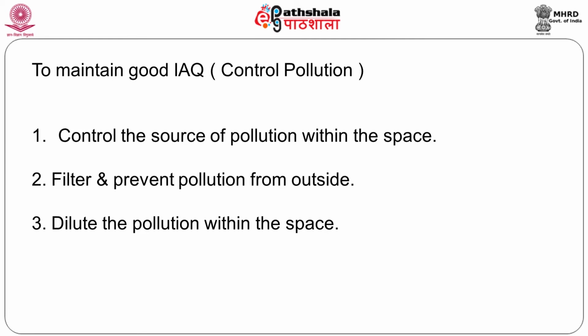This was source control. Now, if you look at the other form of control, in certain parameters you cannot control the source. Like for instance, wet mopping a floor. Now, the floor has been wet mopped. The moisture will be liberated all over. You cannot do anything. You cannot put a hood over every area that you mop. Now, that is allowed to come out. Then what do you do? You size your equipment in such a manner that it can handle that kind of humidity which is added on. There the pollution is humidity. Here the pollution was an aerosol liberated by a human body.